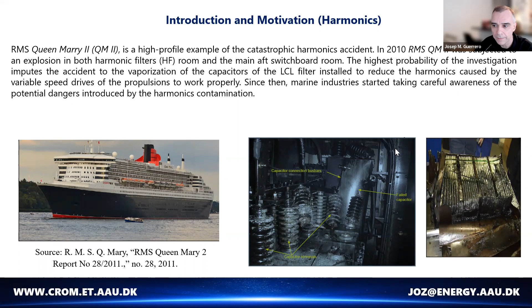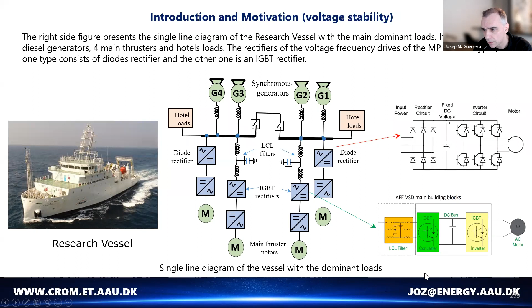This is a key issue to consider, especially with rectifiers. This is just a diode rectifier bridge, and you get huge harmonics, especially the fifth and seventh, which are very important. That's why designs are moving more toward LCL filters with IGBT control.